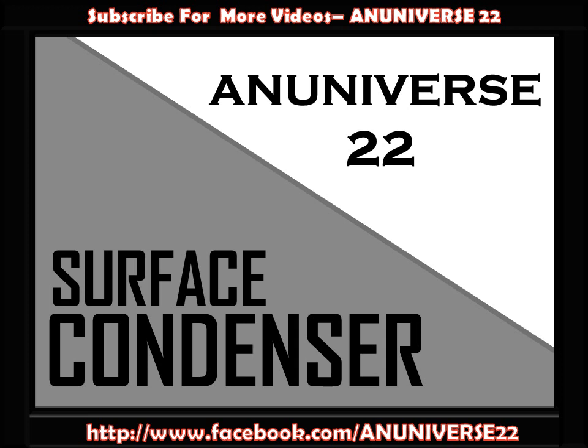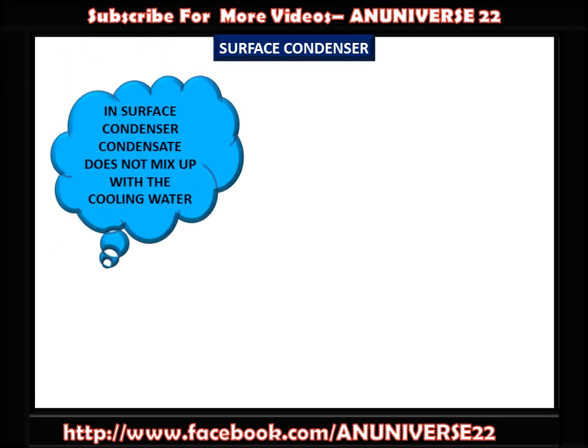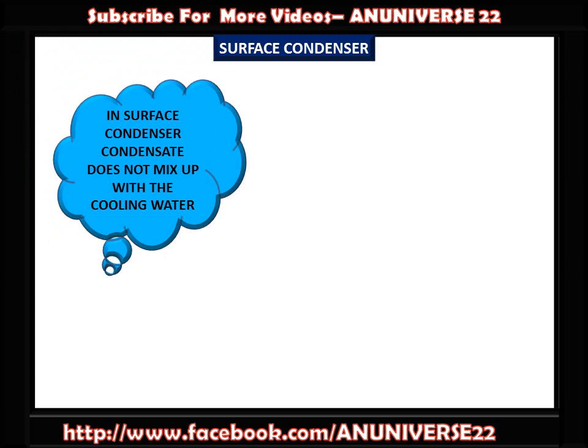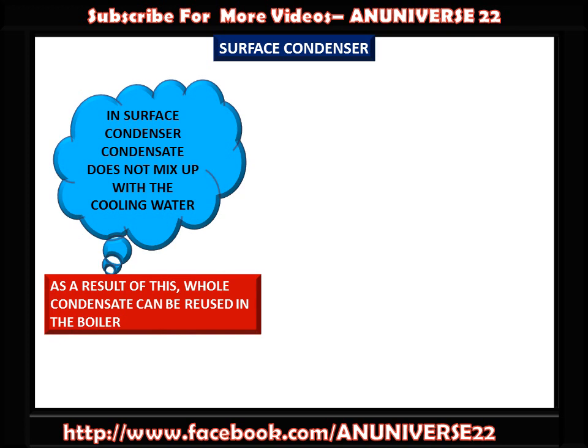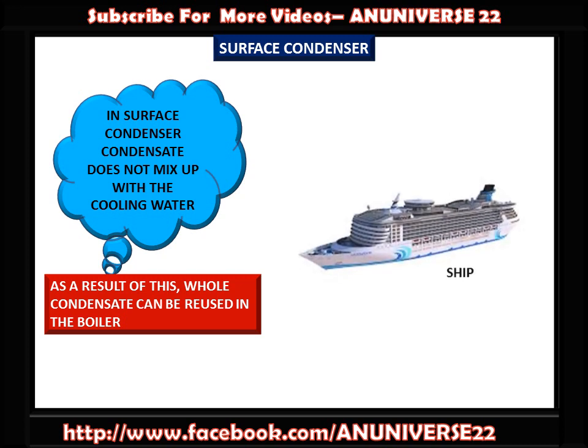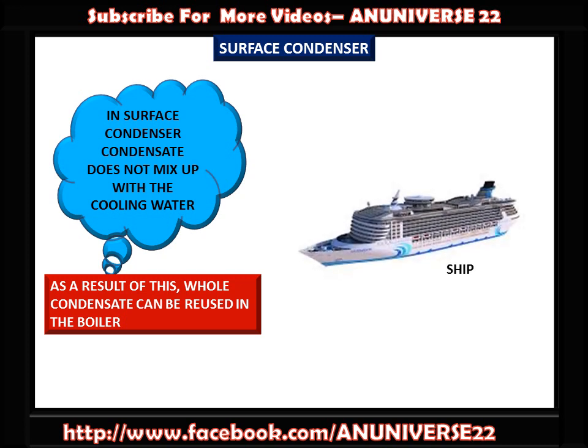A surface condenser has a great advantage over the jet condenser. In a surface condenser, the condensate does not mix up with the cooling water. As a result, the whole condensate can be reused in the boiler. This type of condenser is essential in ships which can carry only a limited quantity of fresh water for the boilers. It is also widely used in land installations where inferior water is available, or where better quality feed water is to be used economically.